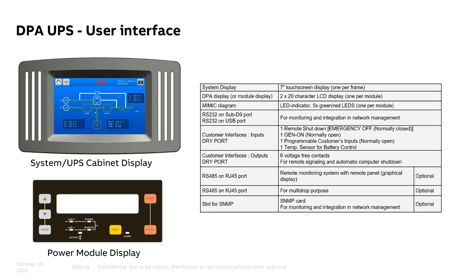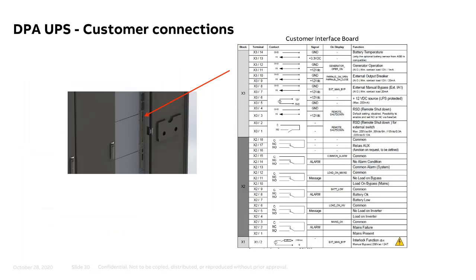Having a small HMI or display on every power module, on every little UPS, makes it a complete UPS. Other than that, communication-wise, and by the way, this is true for all ABB UPSs, not only the modular ones, there's relay, like the good old fashioned. This is what UPSs did when I started in this business. There were typically two standard relays. One was a common fault. Anything would trigger that relay. The other one was battery operation, often wired to a big bell or a horn outside the UPS room.